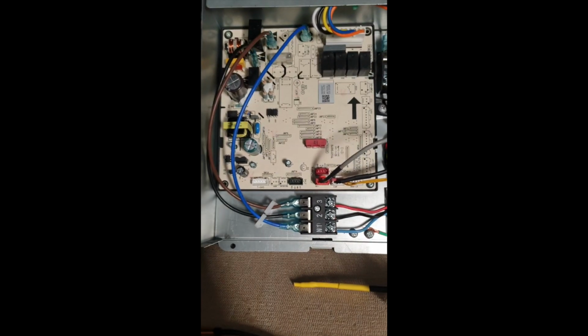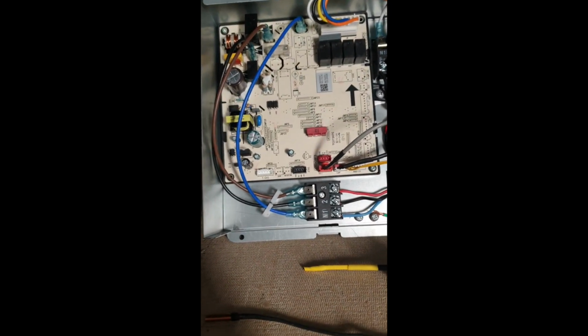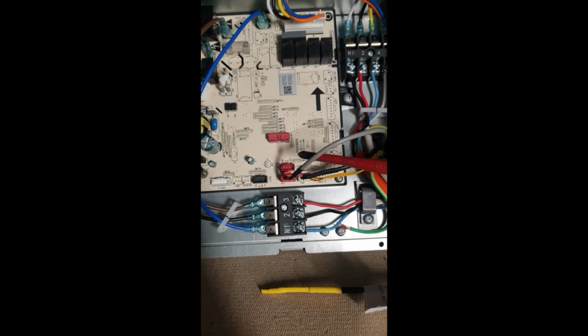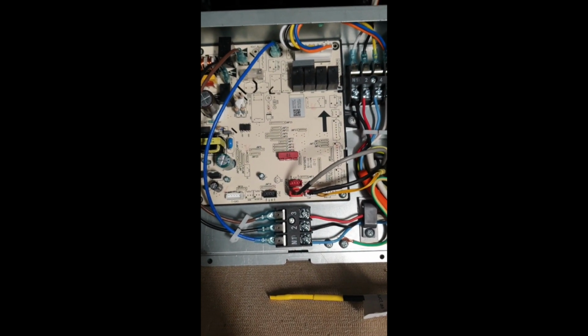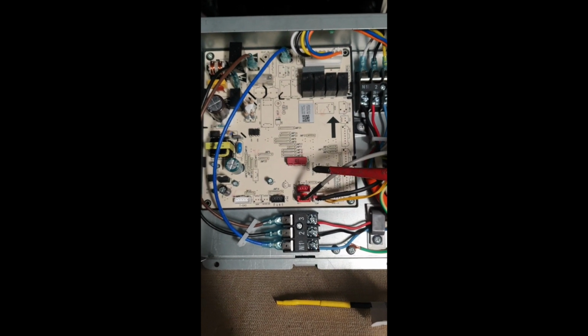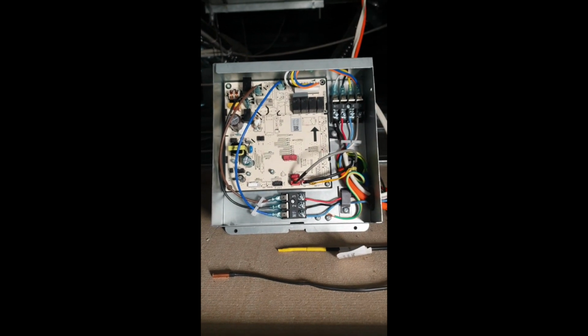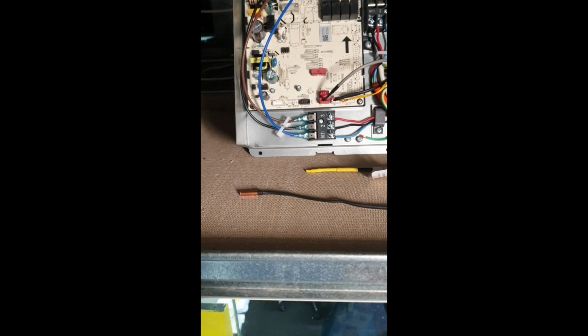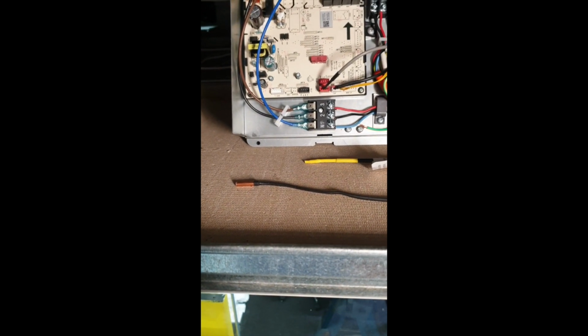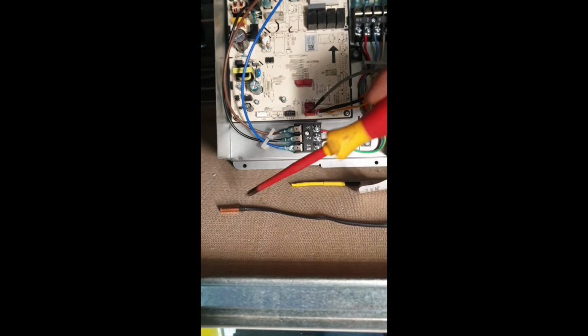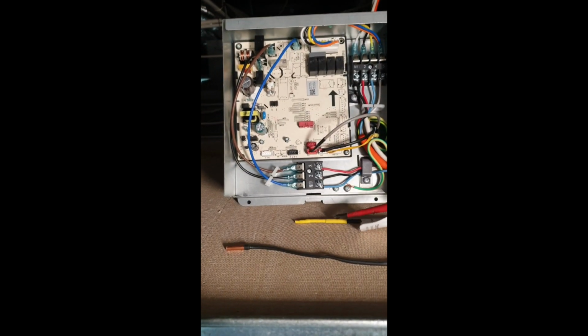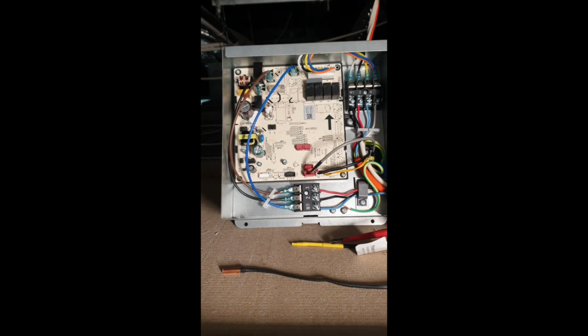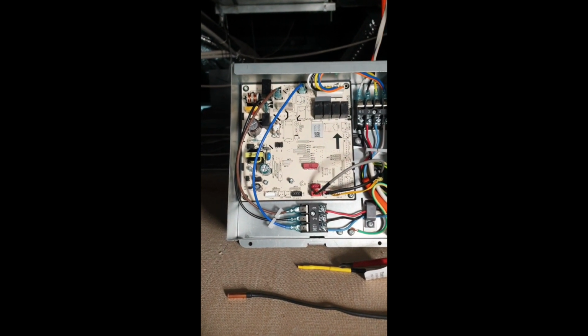So we also have the wired controller somewhere here. Where is that? So this is the wired touchpad controller that will be installed down in the ceiling and return airspace within the zone. So all of the smarts are within this board. We have 2 sensors that we can see here laying on the ceiling tiles at this stage. They're the temperature sensors and if required, the hydrocarbon sensor as well, that will isolate the system in the event of a refrigerant leak.